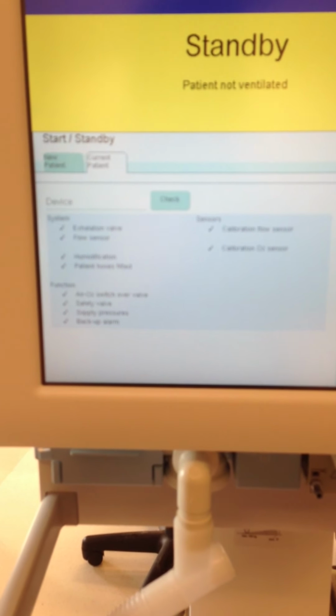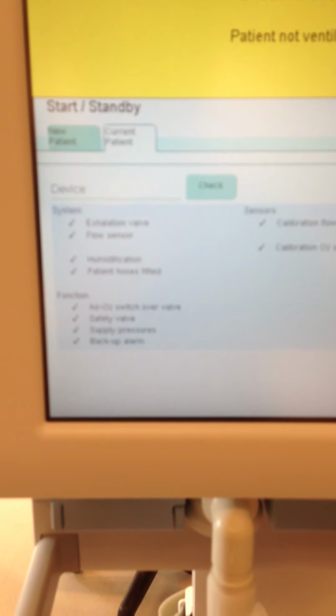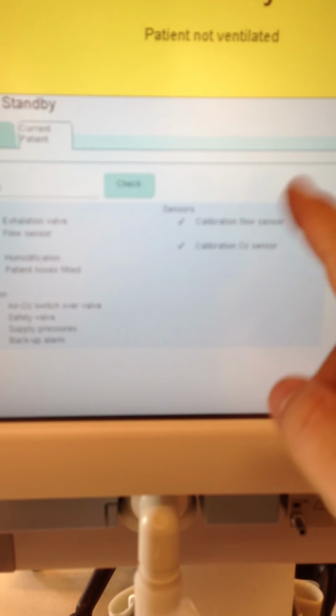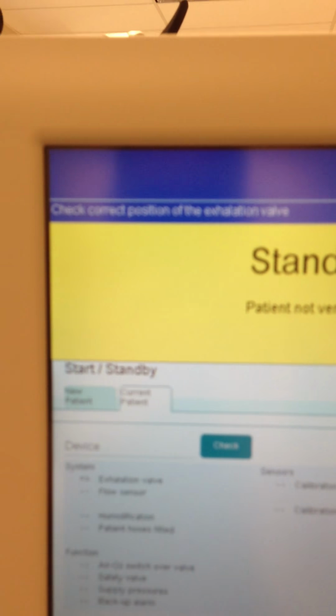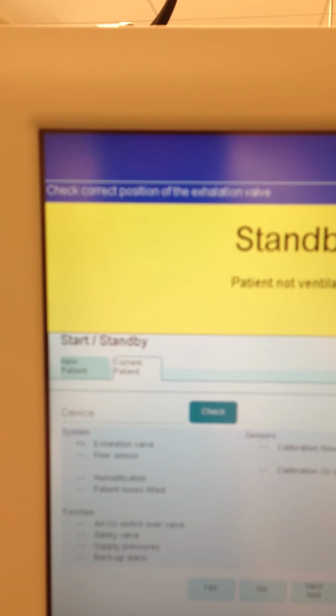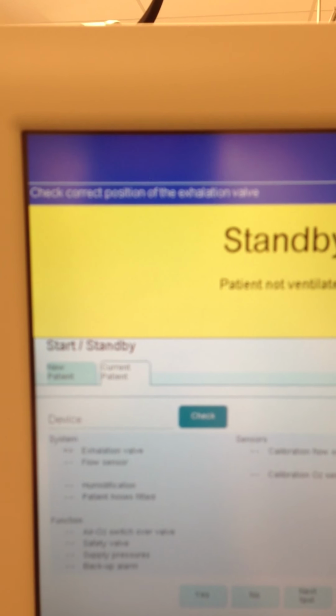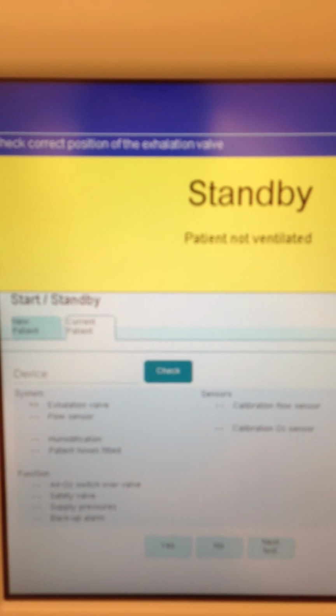And what we want to see is we're going to check exhalation valve, flow sensor, humidification, all of these different functionalities of the different sensors. What we want to see are these check marks beside each of those tests. Okay? So we're going to go ahead and hit check. And up at the top you'll see a prompt that says check correct position of the exhalation valve. Well, we've already done that, we've assembled it.